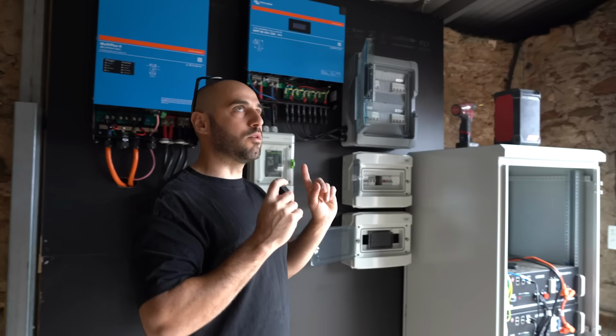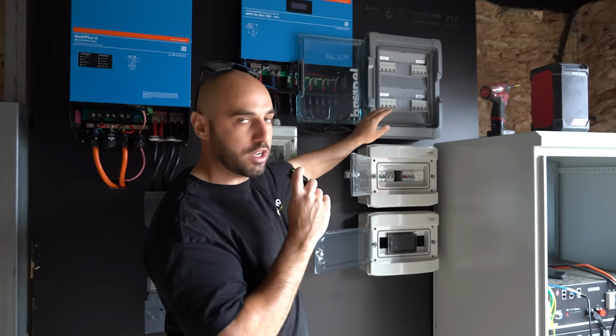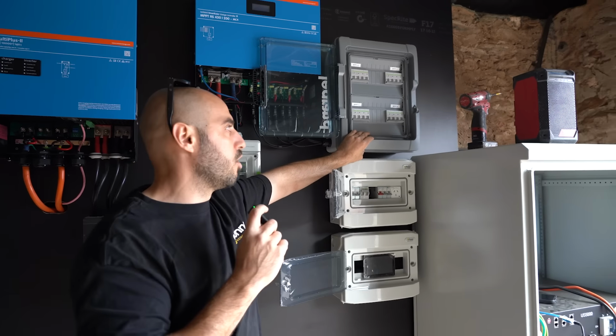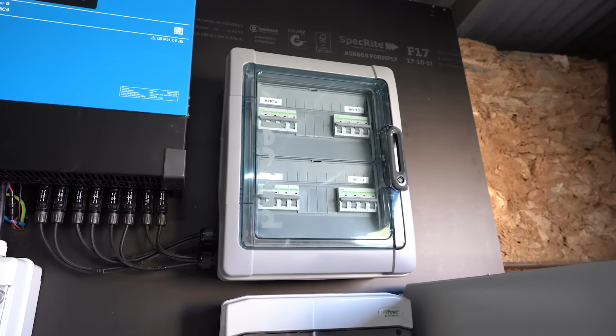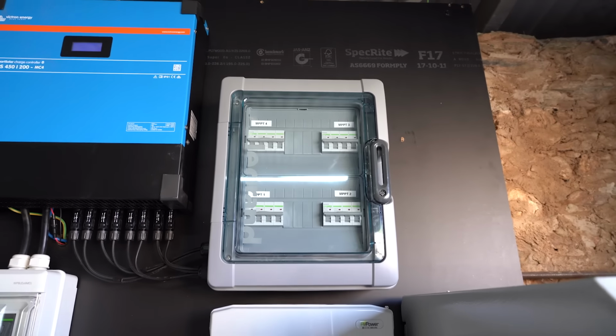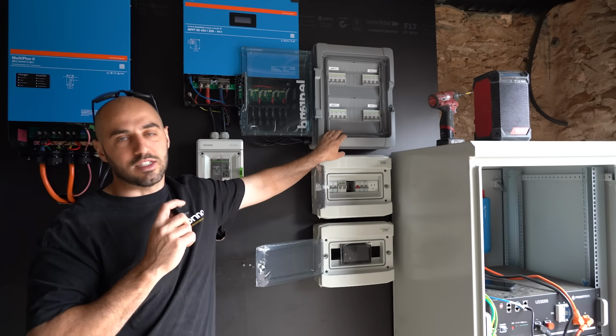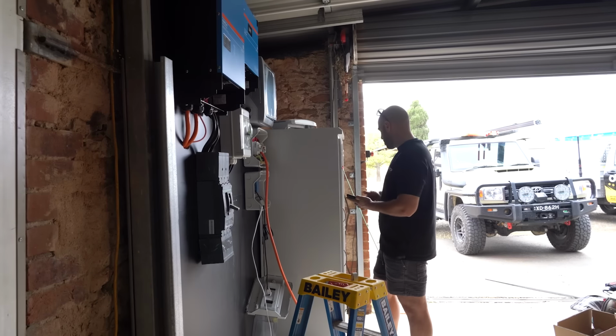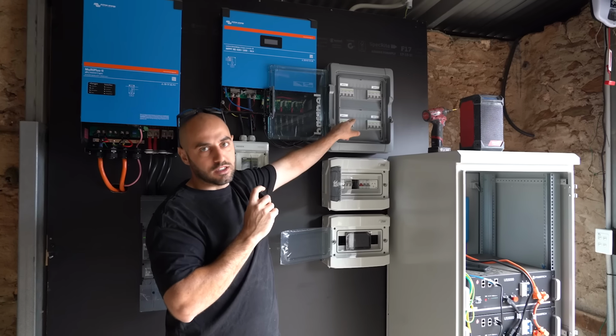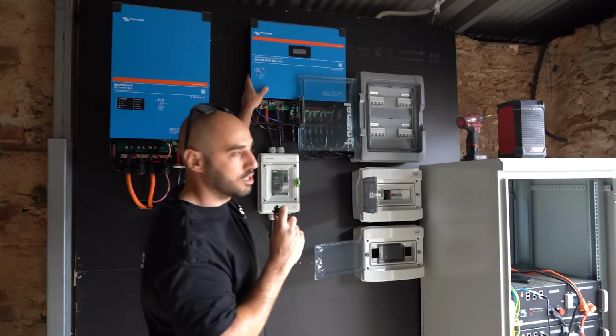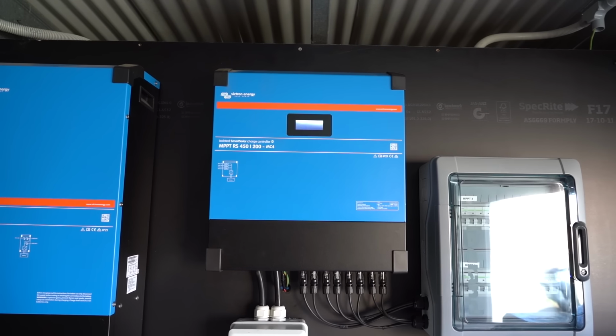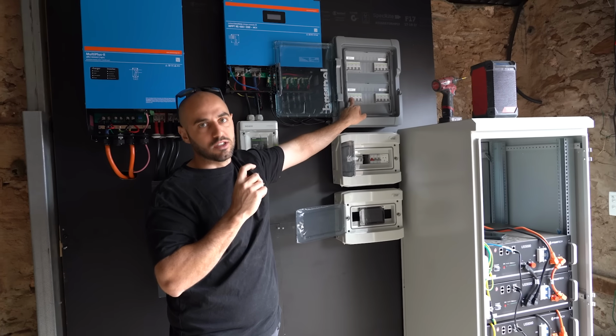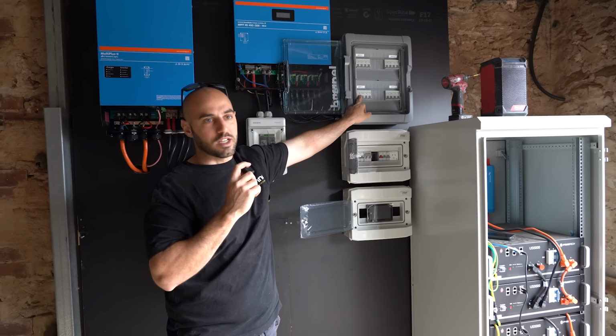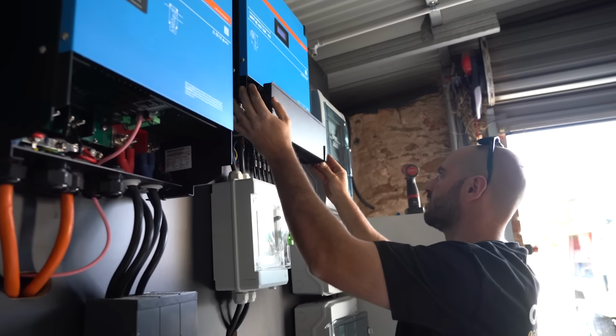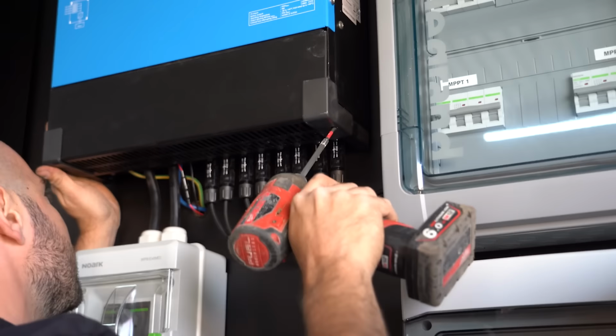Over here we finished up the roof, doing the DC isolators. We used a nice Legrand or similar IP rated enclosure, with some Noark DC isolator circuit breakers, really good 4-pole units. We've got 4 trackers, so 4 MPPTs on this big RS 450-200 controller, with 4 circuit breakers to accommodate the MPPT. This can take about 15 kilowatts of solar in for maximum charging.